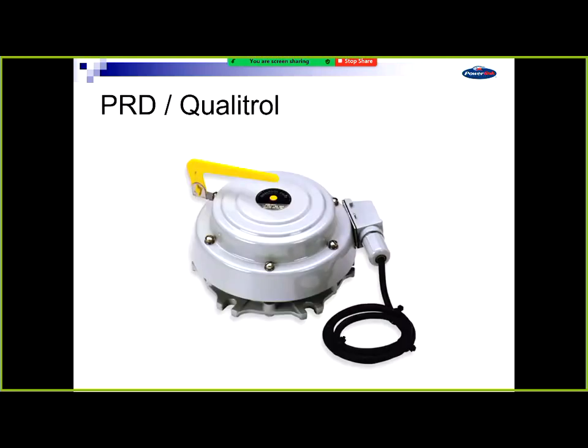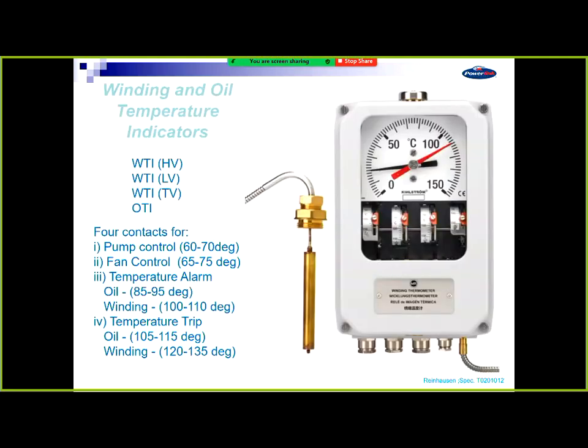And relay contacts are connected to trip the transformer. That's just what they look like. They're mounted on the side of the transformer, and the transformer manufacturer puts them on the transformers. There's winding and oil temperature that we have, and there's HV, LV and TV tertiary winding and oil temperatures. So we have 4 contacts on them. The first is to start and stop the pumps and fans, and then we get into temperature alarms, which say the transformer's getting a bit hot, the fans are all on, you're still heating up. Mr. Operator, you need to take some load off somewhere because we're getting too hot. You need to do something.